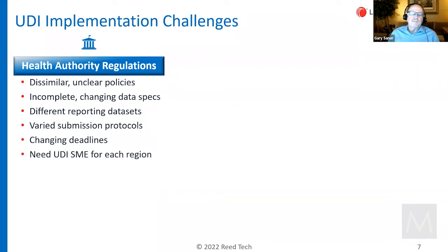I believe we can roll these challenges for UDI into 3 different categories. One of them is external to your company, and it has to do with the health authorities. Unfortunately, it's not nice, clear harmonization. The European Union did not do a cookie cutter of the FDA, nor did South Korea, China, whatever. It seems like all of them rearranged things and made it customized. There's some core commonality, but when you get down to the weeds, unfortunately, it's quite different. And there's a number of different problems there. Policies are different. The data specs themselves are different, various deadlines and so on.